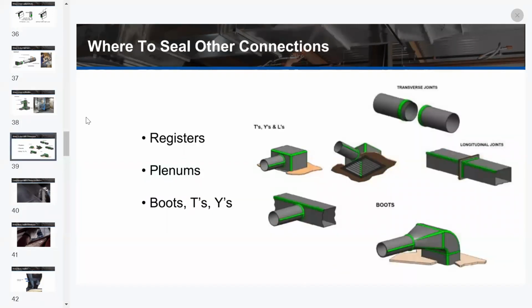Other connections, right? If you're talking about boots, T's, Y's, registers, plenums, you've got the pictures here with the green showing where you should seal. It's just important, when you're looking at typically residential, a lot of your leakage is going to be at the registers. You're going to get leakage in the plenums, the branches, and even the duct wall penetrations too.